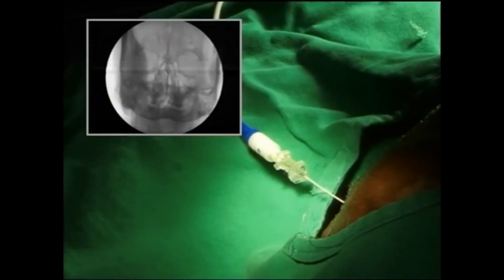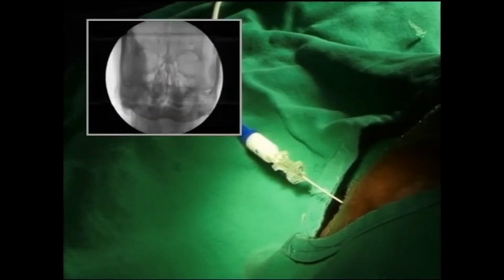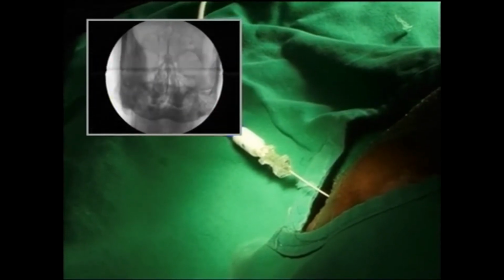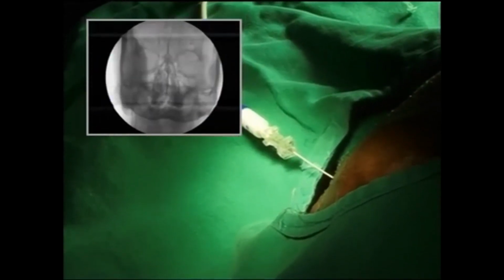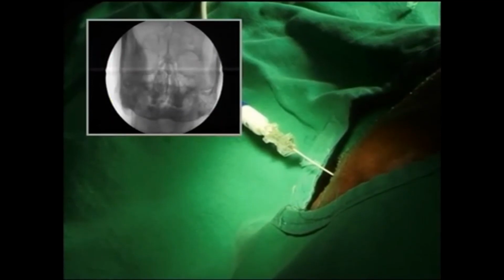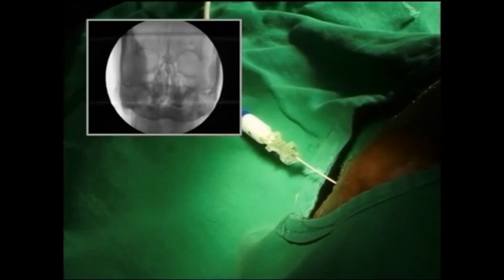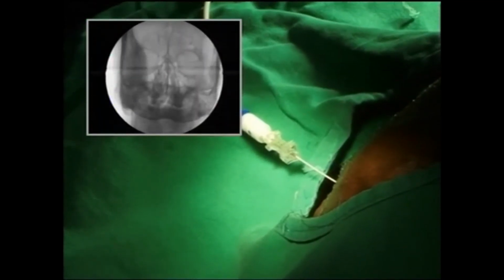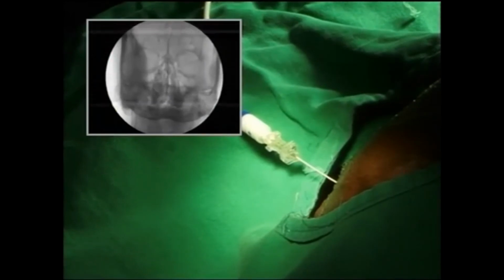Pankaj, in my practice, I use a neurotherm machine. Neurotherm machine, you can set it usually at 90 seconds. So if I'm doing a thermal ablation, I set it at 90 seconds at 80 degrees centigrade. But the range is 60 seconds to 120 seconds. You can choose. But normally what happens? The tip temperature takes around 8 to 10 seconds to reach.